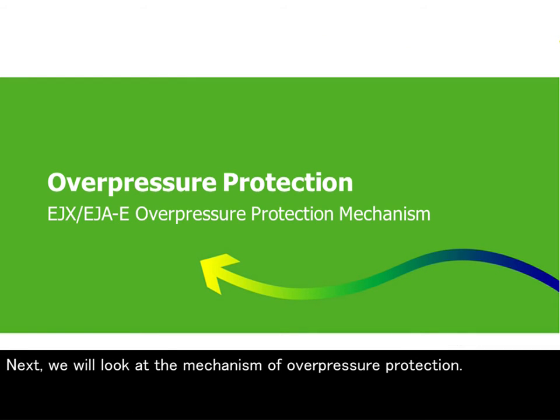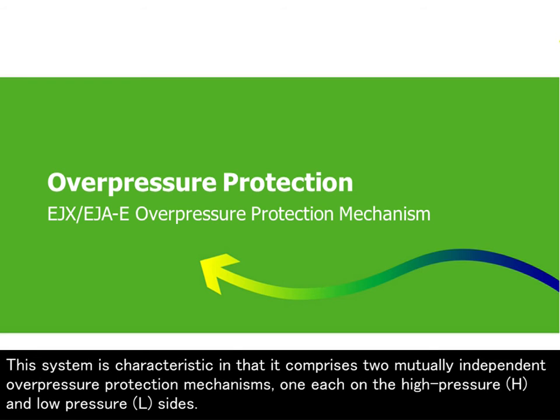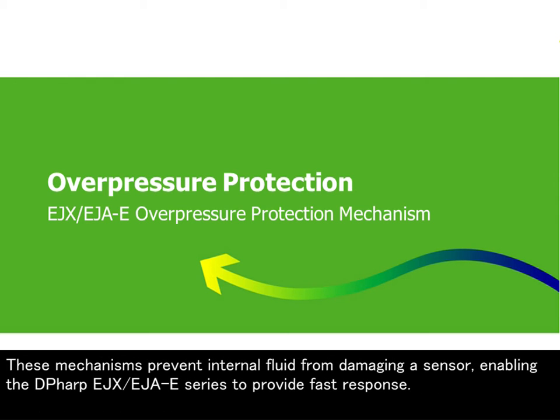Next, we will look at the mechanism of overpressure protection. This system is characteristic in that it comprises two mutually independent overpressure protection mechanisms, one each on the high pressure (H) and low pressure (L) sides. These mechanisms prevent internal fluid from damaging a sensor, enabling the DPharp EJX/EJA-E series to provide fast response.